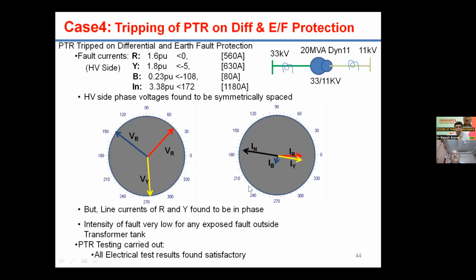Now, this case number 4 is quite interesting. This is again about a tripping of a 20 MVA transformer on differential and earth fault protection. In this case also, we received quite low values of fault currents. See, for this particular 33 by 11 kV transformer, ideally my fault current on the 33 kV side is around 10 to 12 kiloamperes, and on the 11 kV side it is around 6 to 7 kiloamperes. But what fault currents were recorded during tripping of this transformer on the HV side, the currents were merely 560 amperes and 630 amperes, and the B phase was recording simply the load current which was flowing at that time, and neutral current was quite high.